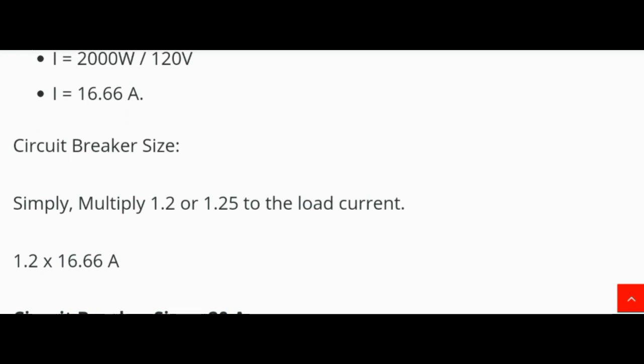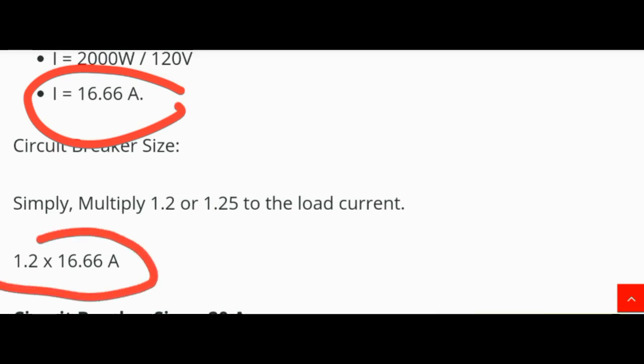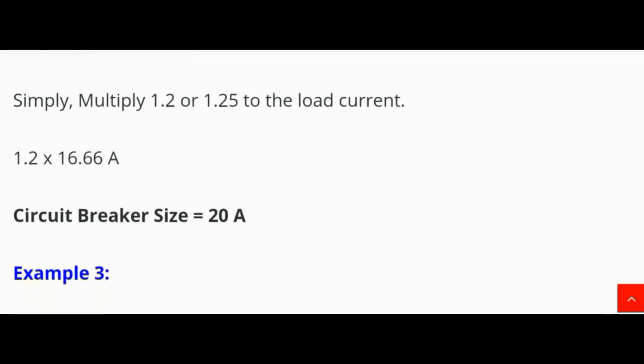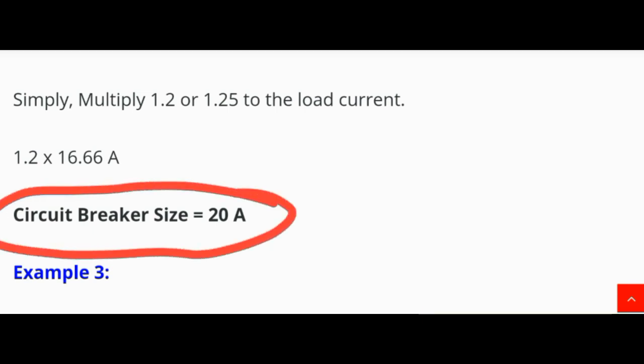Circuit breaker size: multiply 1.25 by the load current. So CB size = 1.25 × 16.66 A = approximately 20 ampere. Therefore, the circuit breaker size is 20 ampere.